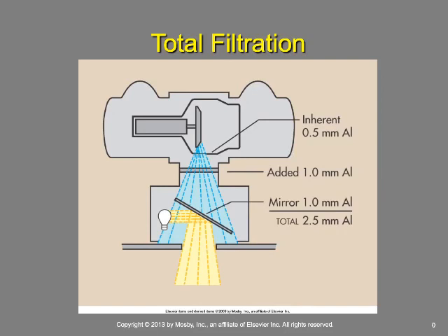Now I want to just point out real quick, and we'll spend a whole chapter talking about filtration, that I'm not talking about you adding anything to the X-ray beam. So I think here, this is a filter that might be added to the X-ray tube manually. So it would be a compensating filter, right? I would actually add this myself to the X-ray tube, and I would call it a compensating filter. But what I'm talking about is the total filtration of the X-ray tube system itself.